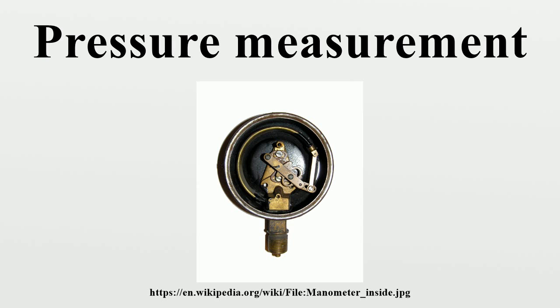For most working fluids where a fluid exists in a closed system, gauge pressure measurement prevails. Pressure instruments connected to the system will indicate pressures relative to the current atmospheric pressure. The situation changes when extreme vacuum pressures are measured. Absolute pressures are typically used instead. Differential pressures are commonly used in industrial process systems. Differential pressure gauges have two inlet ports, each connected to one of the volumes whose pressure is to be monitored. In effect, such a gauge performs the mathematical operation of subtraction through mechanical means, obviating the need for an operator or control system to watch two separate gauges and determine the difference in readings.